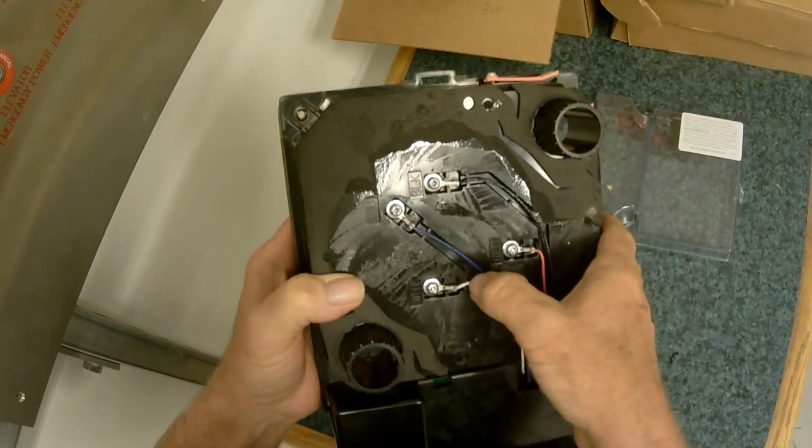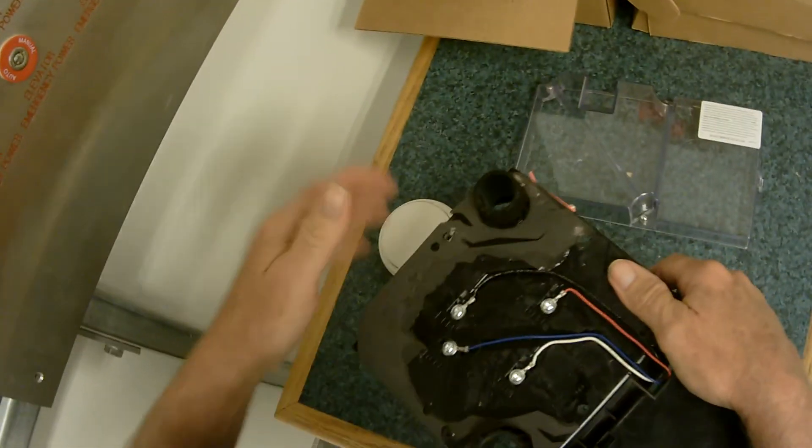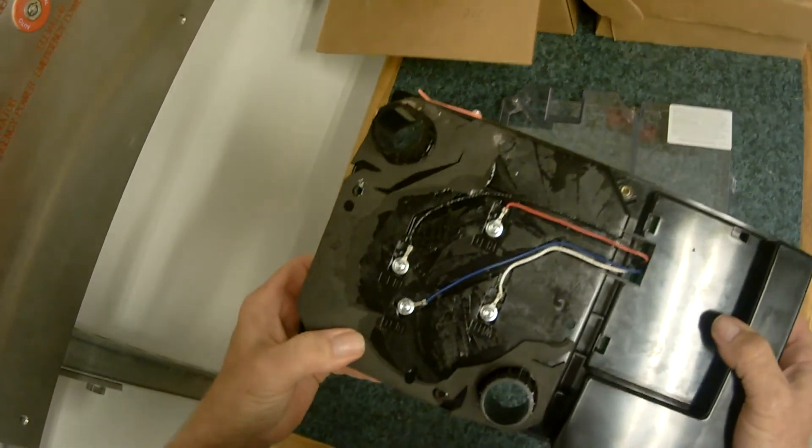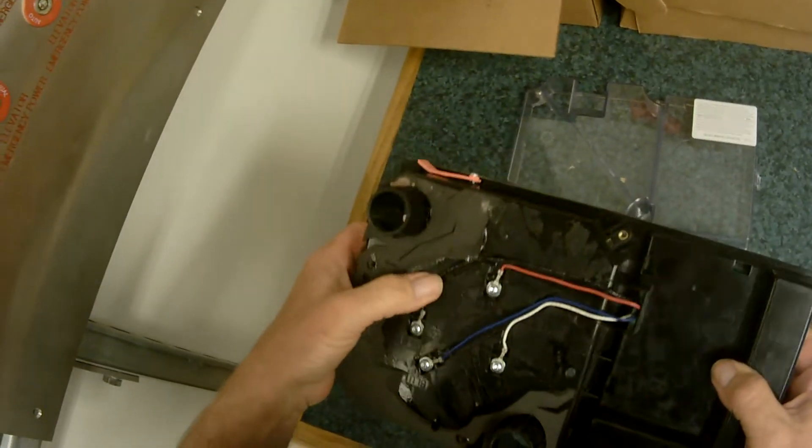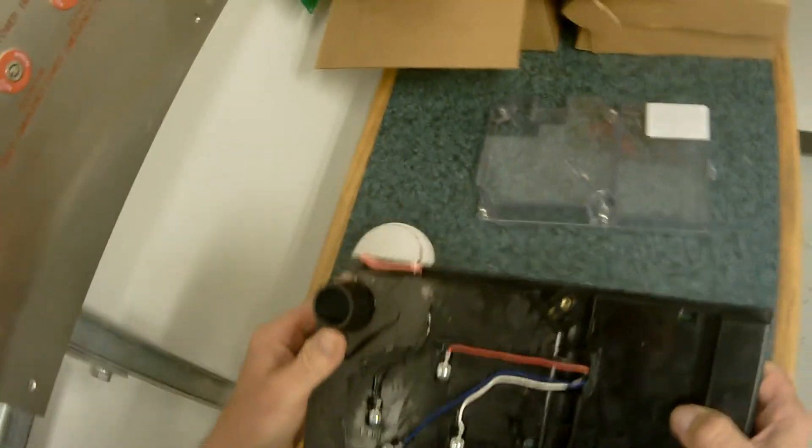Sometimes it's always a good idea to check it. This one's a tough one to do because you have the rubber that gets stuck - the adhesive rubber gets stuck onto the back of it. If you're ever in a pinch and you're experiencing this type of problem, more than likely you'll have to replace the duct detector.